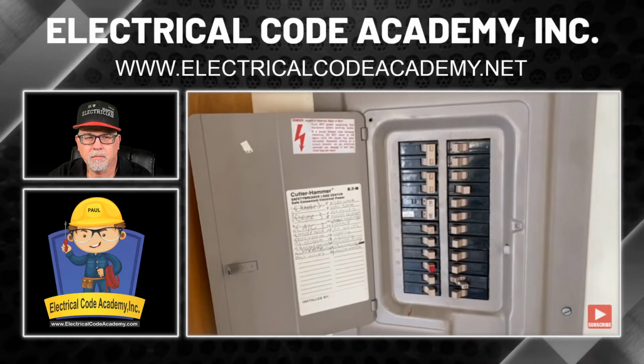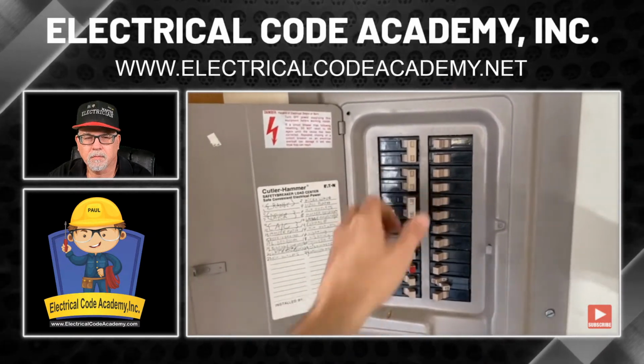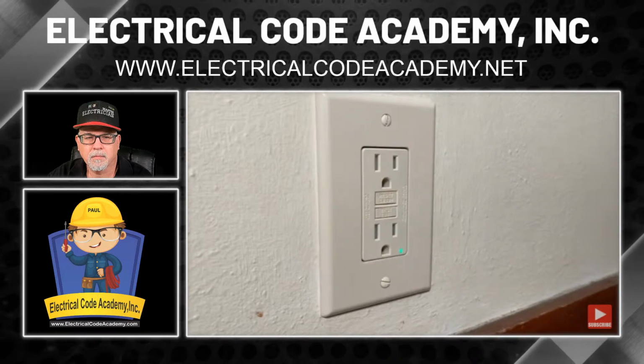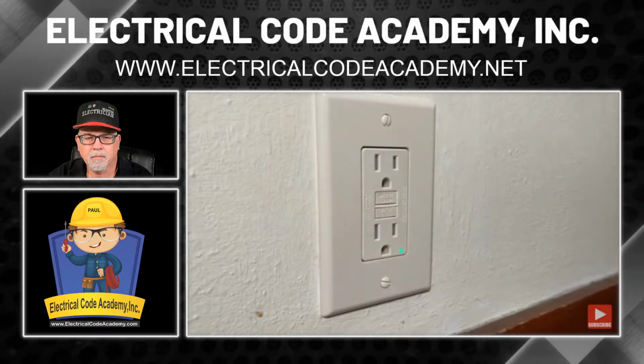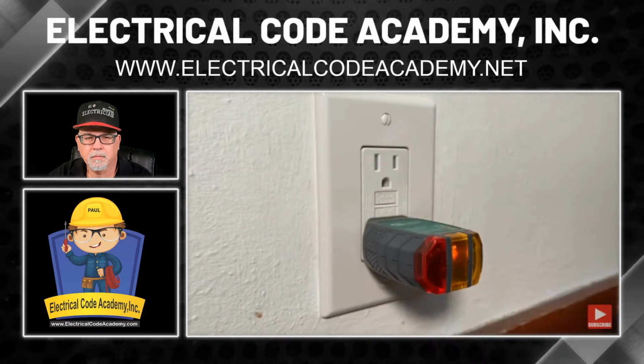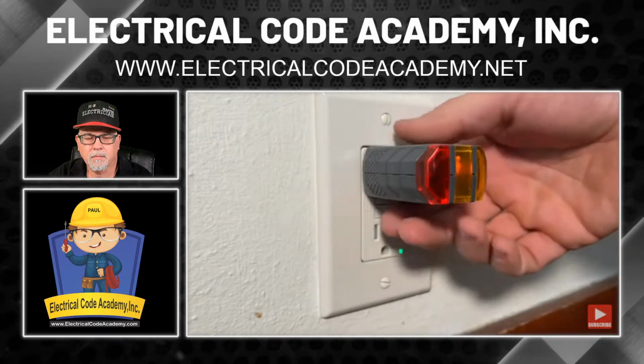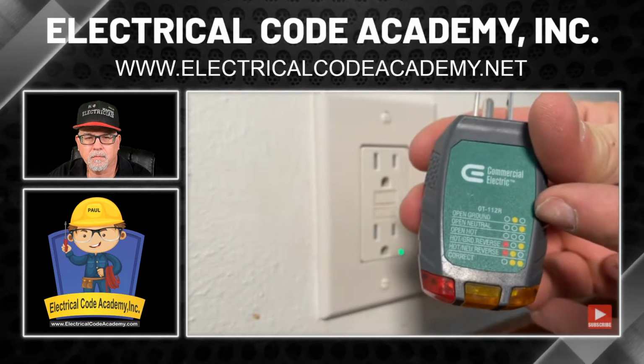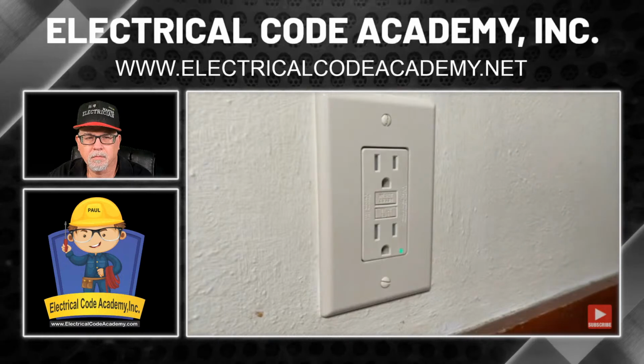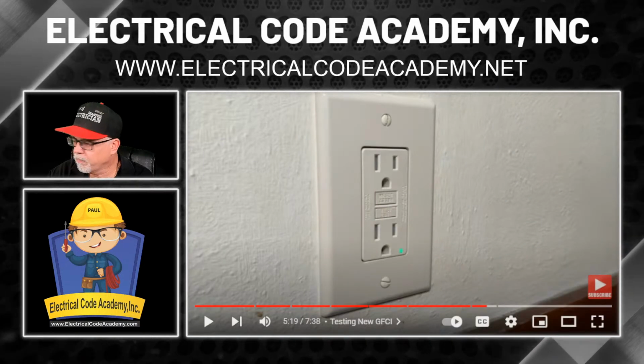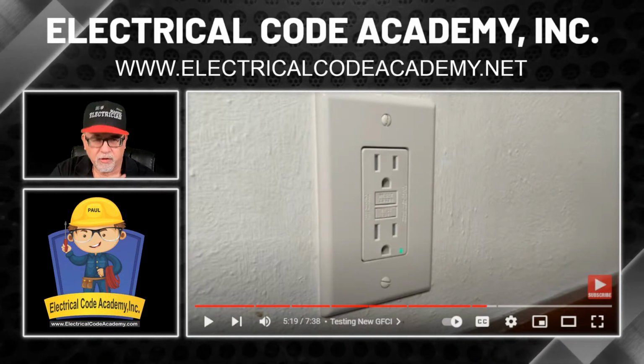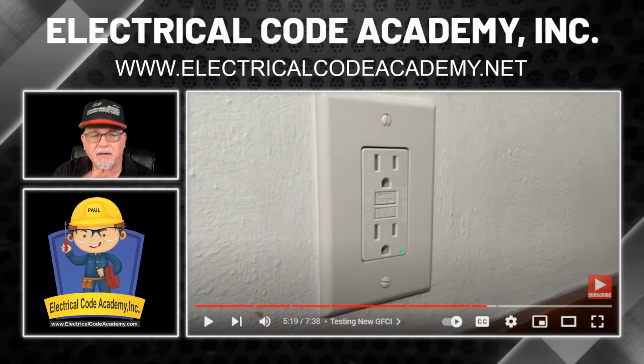So go hit your breaker back to the on position, and we'll press the reset button, testing with our voltage tester. Everything looks good. Also use an outlet tester, where I only have the center LED on, which does mean open ground, which is expected. Okay, all that's true. I would expect an open ground because there's no ground there, obviously.